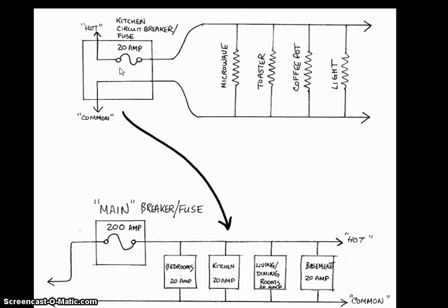What a circuit breaker will not protect you from is an electrical shock, because a circuit breaker only limits the current when it gets up to some value like 20 amps. And I think you've learned in class that in order to kill somebody, you need a much lower amount of current. So really, the purpose of a circuit breaker is to stop the current before the wires get too hot.